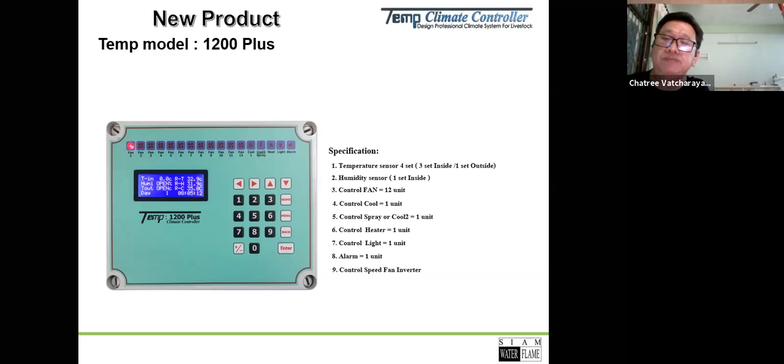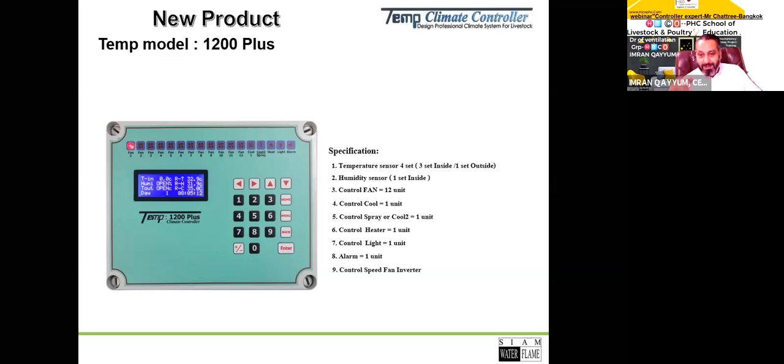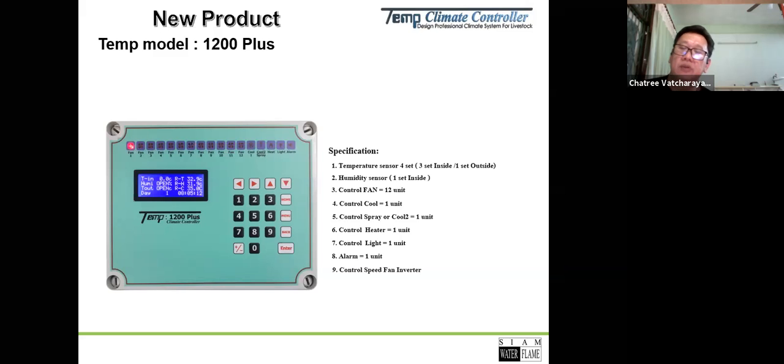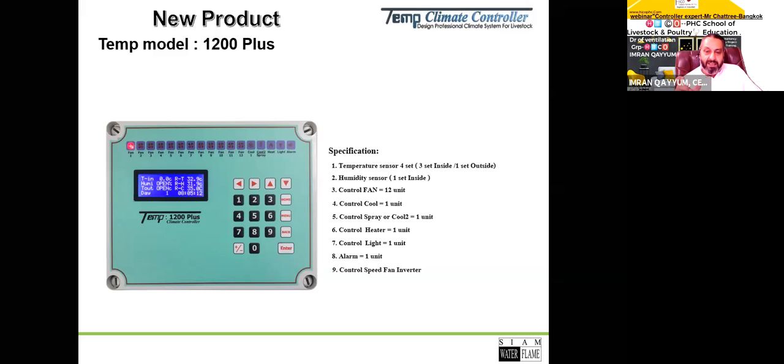Yes, your advice is the same as my advice, because I also advise my clients that you should control your low pressure ventilation on the LPV curve. It means the LPV curve relates your fan operation with the opening of the inlet. This is better, because the life of the pressure sensor is also very short, 2 years, and mostly before 2 years it has some problems.